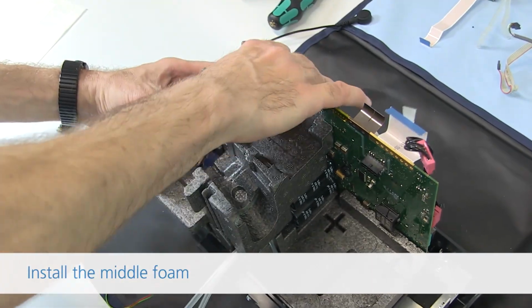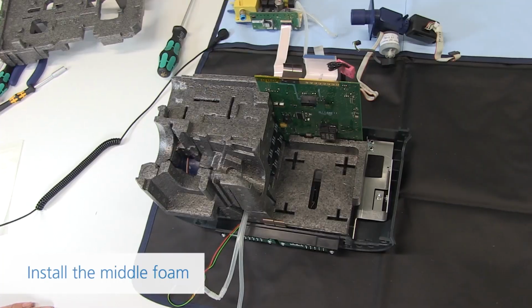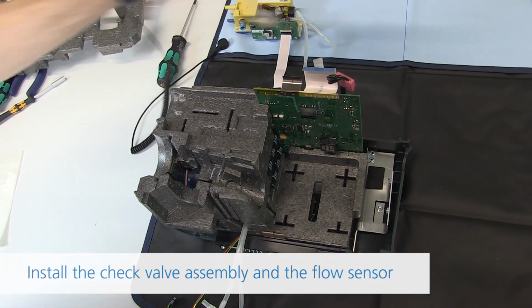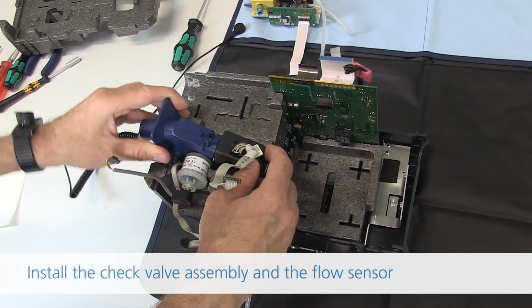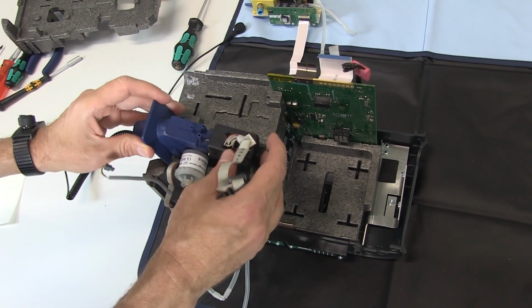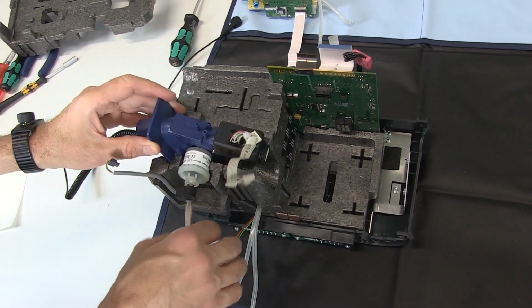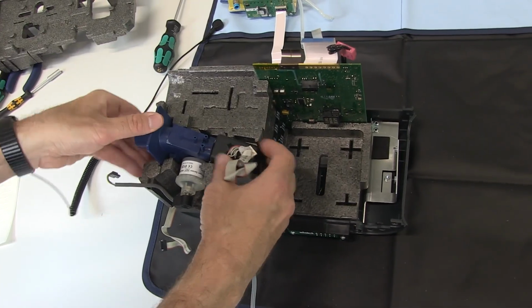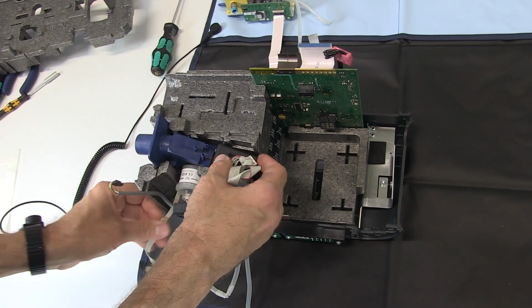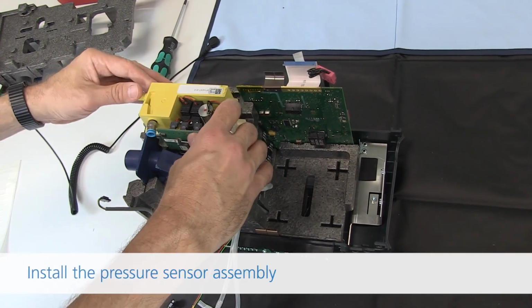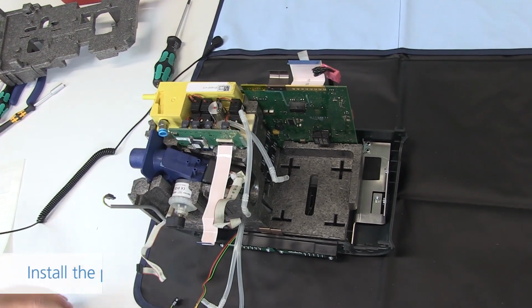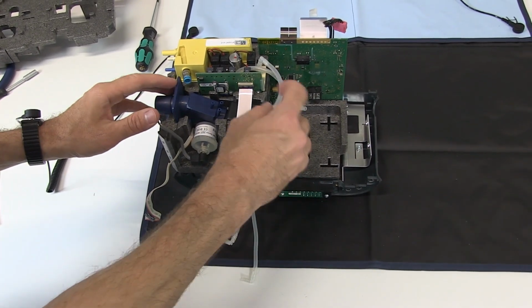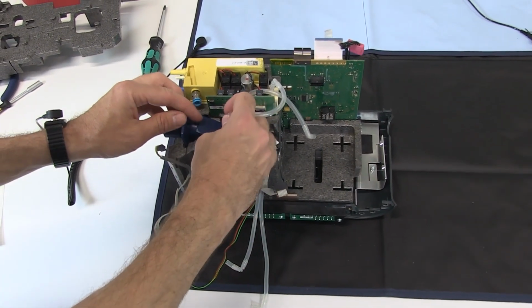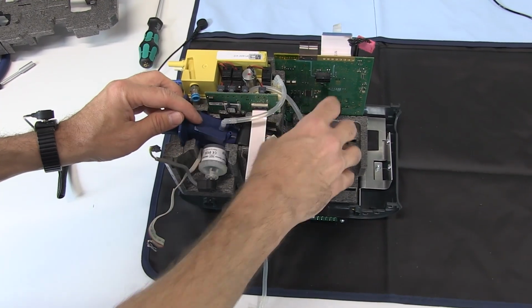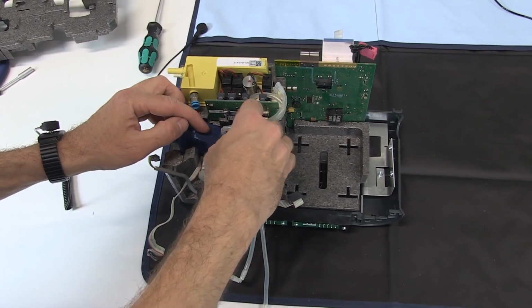Install the middle foam. Install the check valve assembly with the flow sensor. Install the pressure sensor assembly. Connect the P-vent monitor tube and the P-vent control tube from the pressure sensor assembly to the respective designated ports on the check valve assembly.